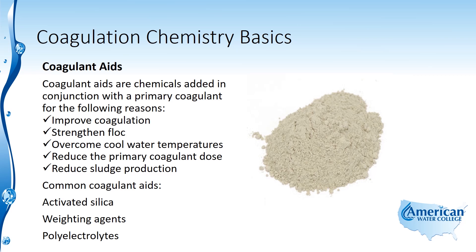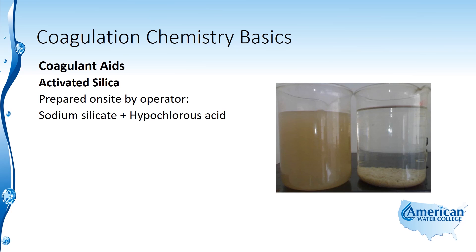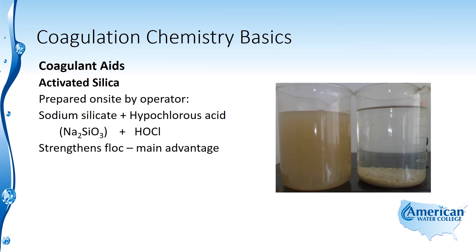We're going to look at activated silica. Activated silica is prepared on site by the operator by combining sodium silicate and hypochlorous acid. The sodium silicate is delivered to the plant and the operator mixes it with hypochlorous acid to form activated silica. It is used primarily to strengthen the floc — that's the main advantage — keeping the floc from breaking apart or shearing so that it will settle out.